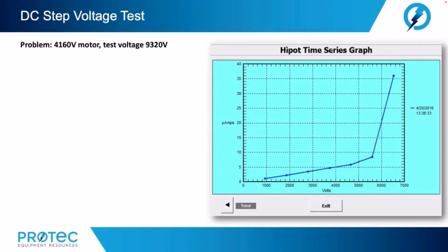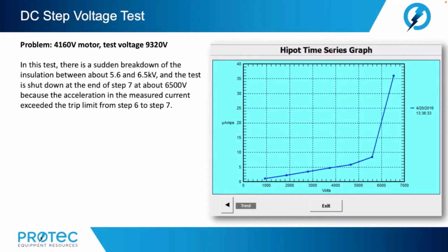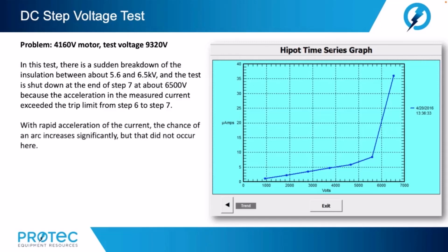Now, this test shows a problem. A 4,160 volt motor being tested at 9,320 volts. In this test, there is a sudden breakdown of the insulation between about 5.6 and 6.5 kV, and the test is shut down at the end of step 7 at about 6,500 volts because the acceleration in the measured current exceeded the trip limit from step 6 to step 7. With rapid acceleration of the current, the chance of an arc increases significantly, but that did not occur here.